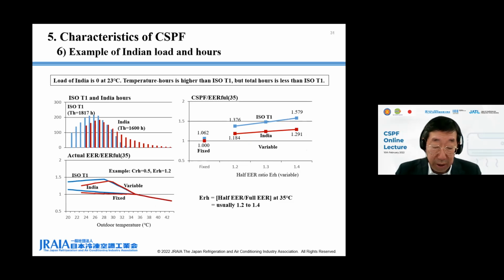This page shows the load and hours for labeling of India. The upper left figure shows ISO T1 and Indian temperature hours. ISO T1 load is 0 at 20 degrees C, but the load of India is 0 at 23 degrees C. Temperature hours of India is higher than ISO T1, but total hours of 1,600 is less than 1,817 of ISO T1 hours.